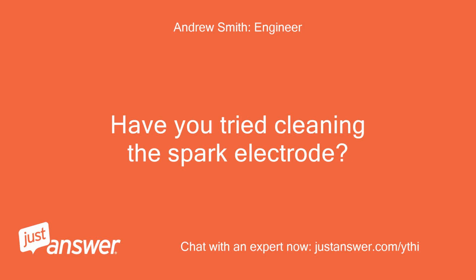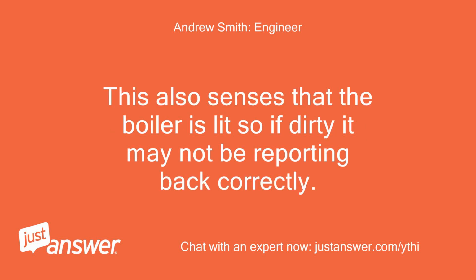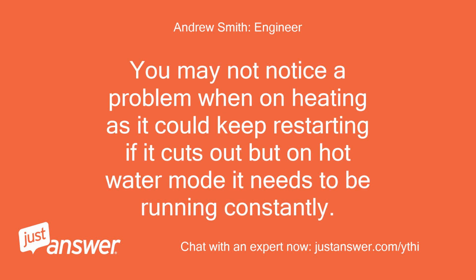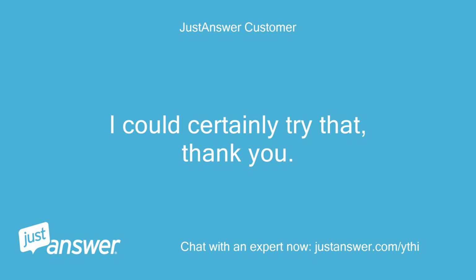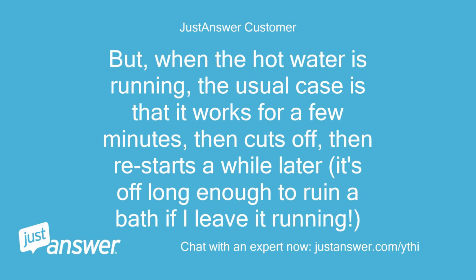Have you tried cleaning the spark electrode? This also senses that the boiler is lit, so if dirty it may not be reporting back correctly. You may not notice a problem when on heating, as it could keep restarting if it cuts out, but on hot water mode it needs to be running constantly. I could certainly try that, thank you. But, when the hot water is running, the usual case is that it works for a few minutes, then cuts off, then restarts a while later. It's off long enough to ruin a bath if I leave it running.